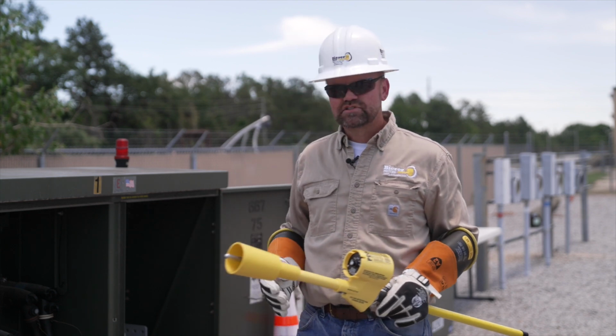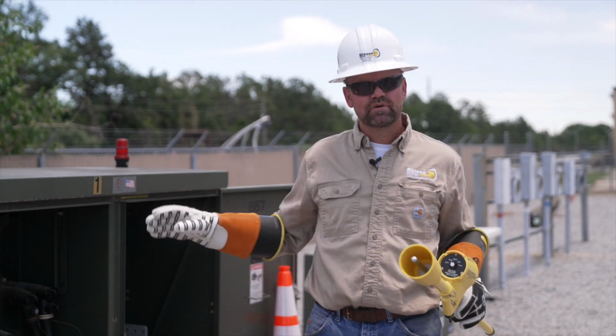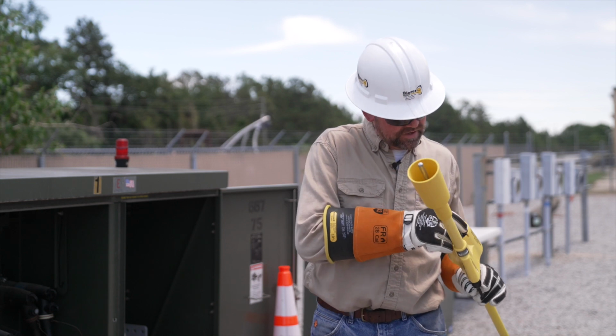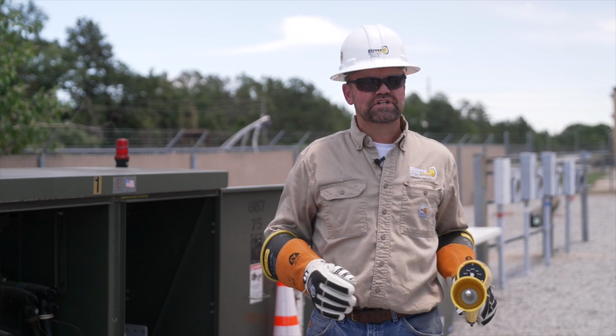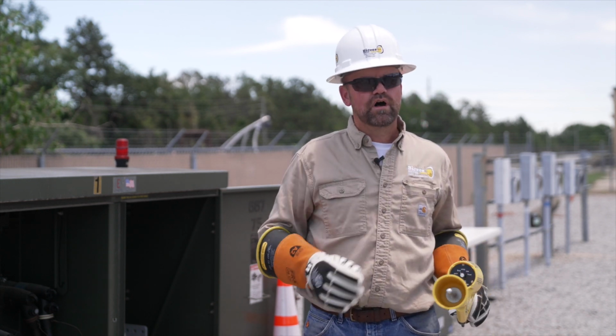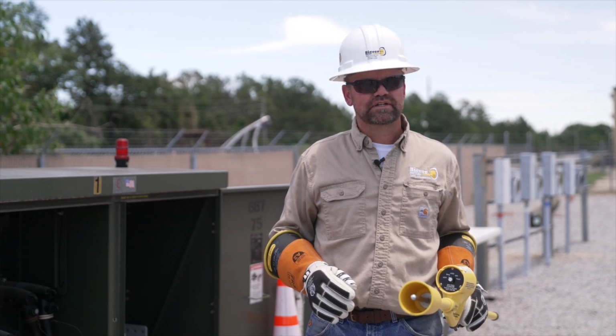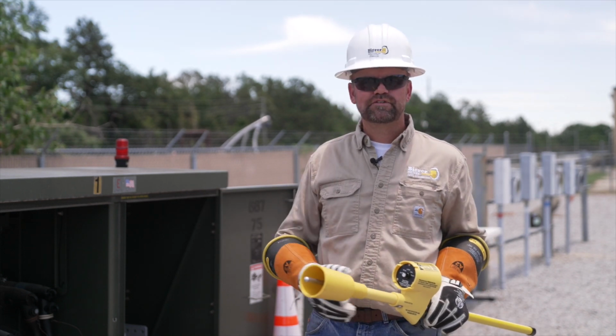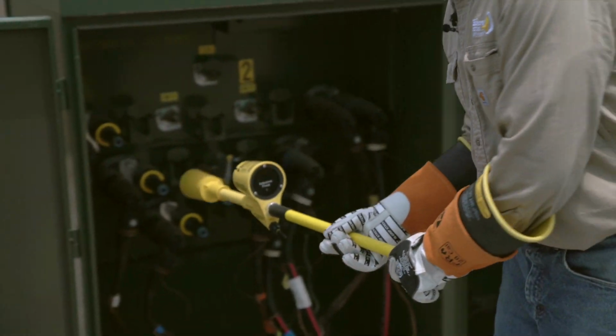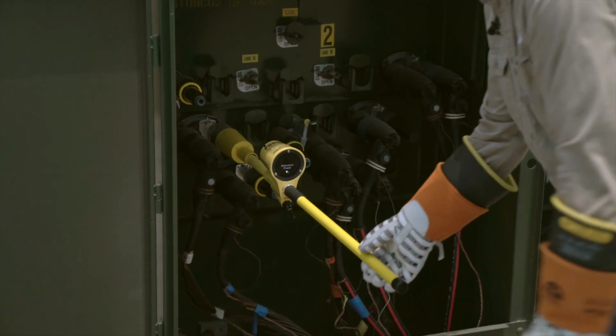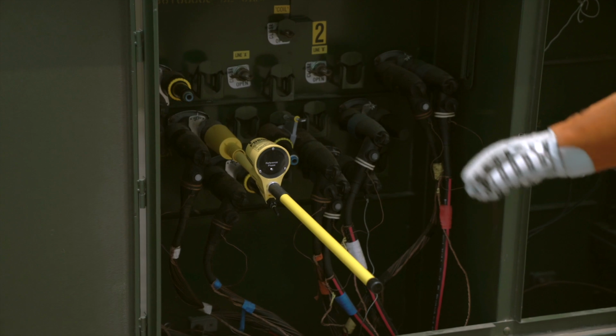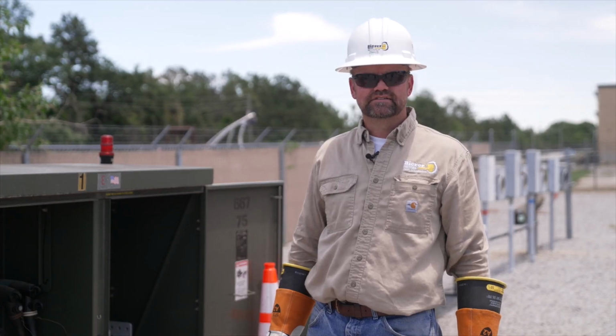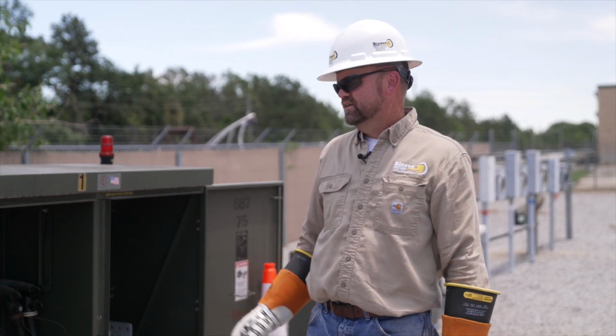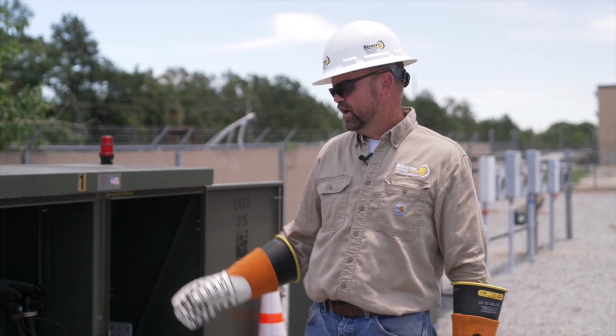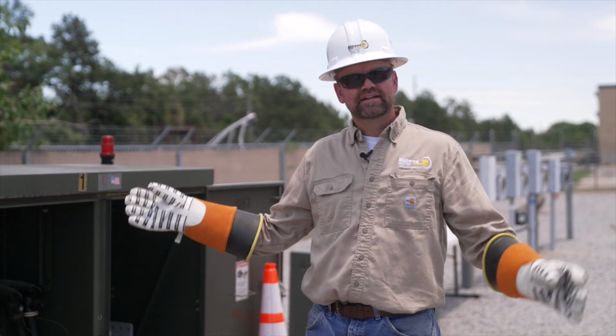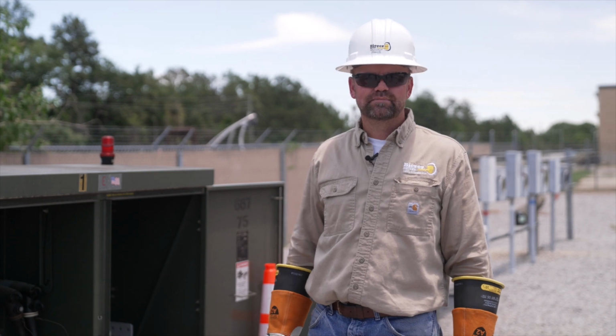I'm going to insert this reference probe into this URD bushing. I'm going to have the device in the DEG switch position, and the meter probe will also be in the DEG switch position. And again, I'm going to pick any one of the 3 phases, insert the reference probe. I do in fact have a white light, so I know this bushing is in fact energized. It at least has 50 volts on it, so I can go ahead and phase and determine what phase overhead is the same phase as my URD bushing.